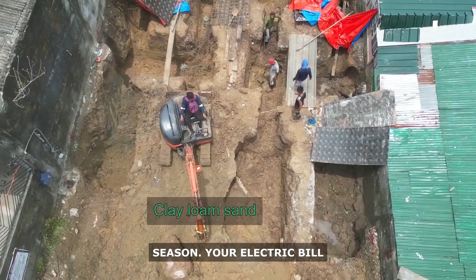Will it replace your central air entirely? In most climates, no. Not if you want to maintain a constant temperature of 68 degrees throughout a brutally hot day. But that is not the goal. The goal is to reduce your reliance on your air conditioner during the cooler parts of the day and the cooler months of summer. Your AC runs hard during the peak afternoon hours when electricity demand is at its absolute maximum, and utility companies are charging premium rates. If you can maintain a comfortable 72 or 75 degrees from dawn until mid-afternoon using only this ground loop, you delay the moment your compressor kicks in by hours.